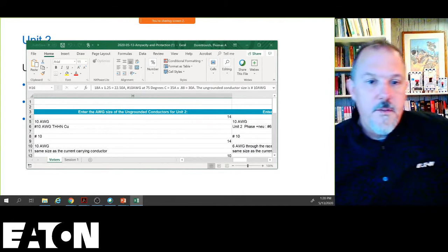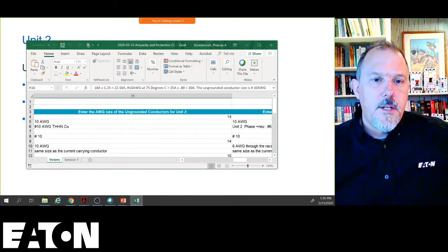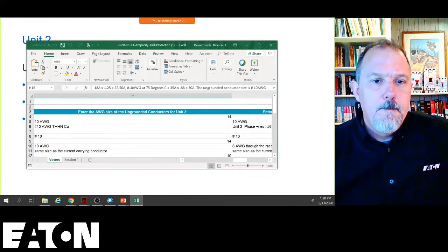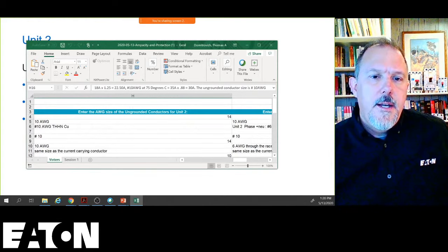Must comply with the requirements in 250.122. It sounds like Tom said otherwise. That is why I posted the question. I'm not sure what raceways get damaged and broken. Okay, I'm looking at the chat on WebEx now. 110.14 pushes you to 60 degrees C. If more than one equipment grounding conductor exists, they all must comply with 250. Are you saying that where I install a wire type EGC and a metal raceway that is an EGC, I can make the wire EGC any size I want? No one said that. The EGC size must comply with 250.122. That's correct. Even with RMC issues, yep, the raceway gets damaged and broken.